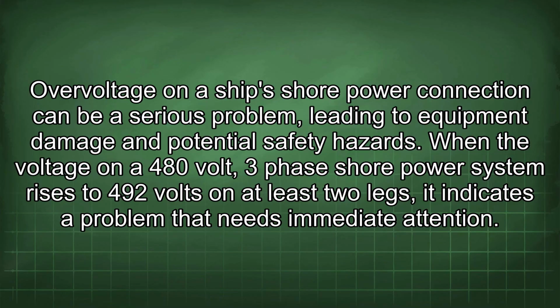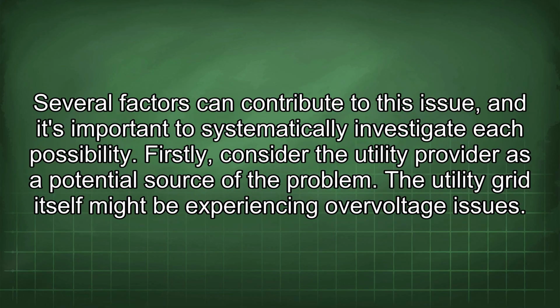Overvoltage on a ship's shore power connection can be a serious problem, leading to equipment damage and potential safety hazards. When the voltage on a 480-volt, three-phase shore power system rises to 492 volts on at least two legs, it indicates a problem that needs immediate attention. Several factors can contribute to this issue, and it's important to systematically investigate each possibility.